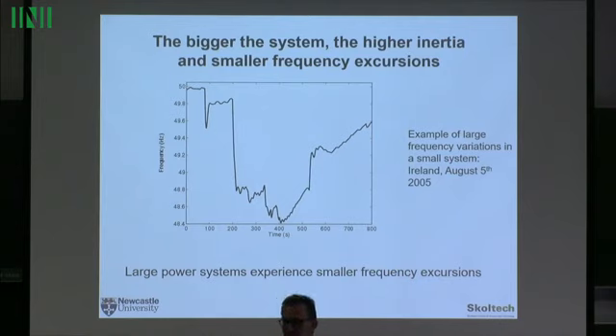But since you ask, I'll tell you. Imagine you have a sudden short circuit. The big generator spinning has no power outlet, so all the power generated goes into acceleration. So they had big resistors to take power out of the generator to stop it losing stability. After unification, they connected everything into the German system, no problem, but this is legacy.